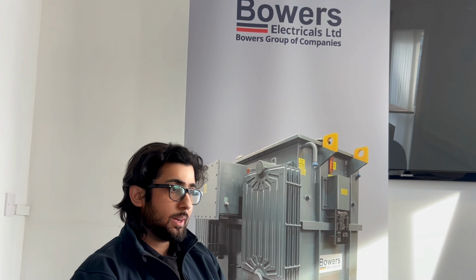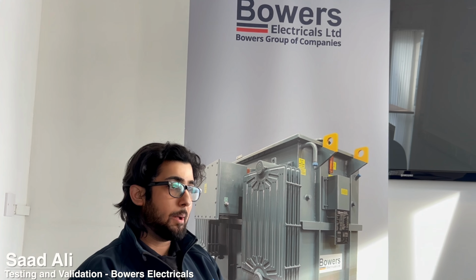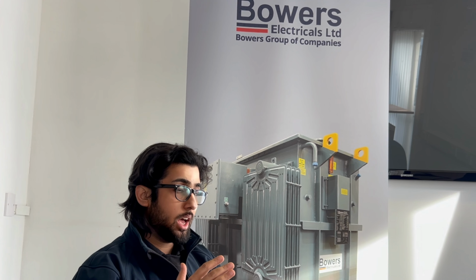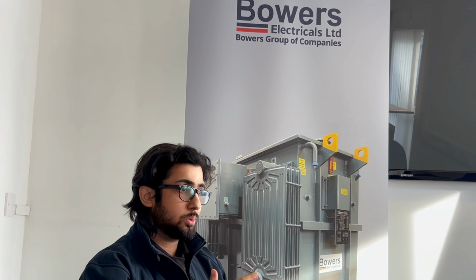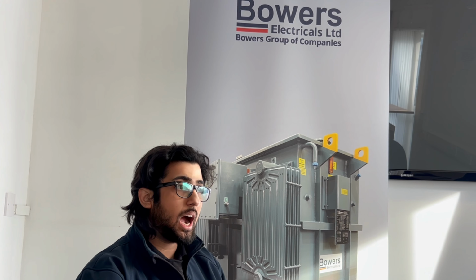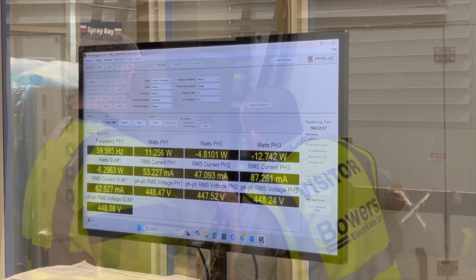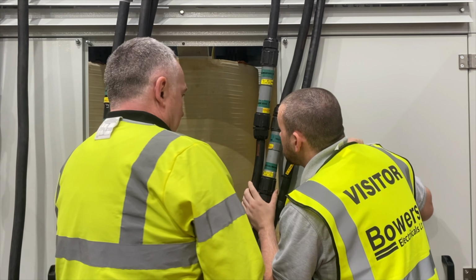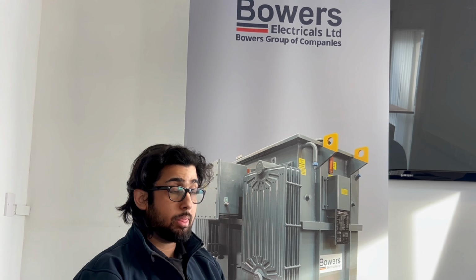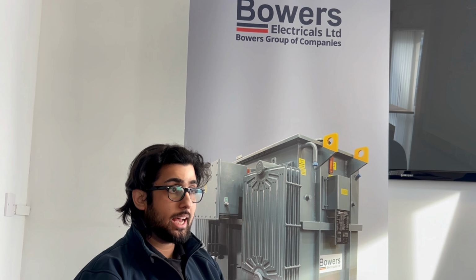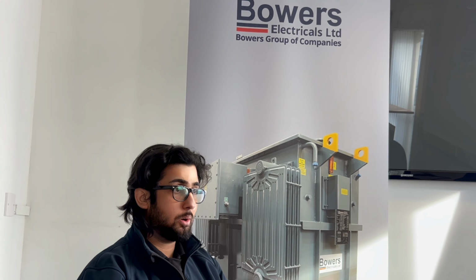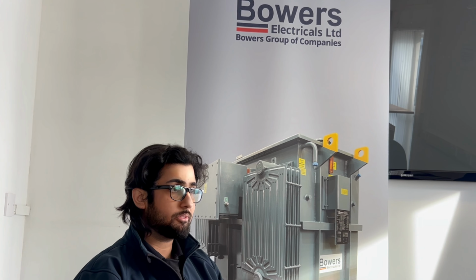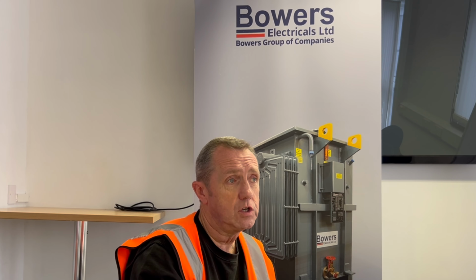From a testing perspective and a system design perspective, getting a unity power factor at source was really important. So our highly inductive transformer, by design, had to counteract the highly capacitive nature of the power electronic based inverters. That was a concerning bit, and that's what I was looking out for. Seeing all that come into play and give us a perfect point of resonance was really reassuring, and that's when I knew we had nailed it. It's a good sign.